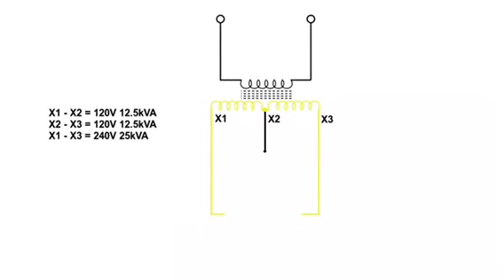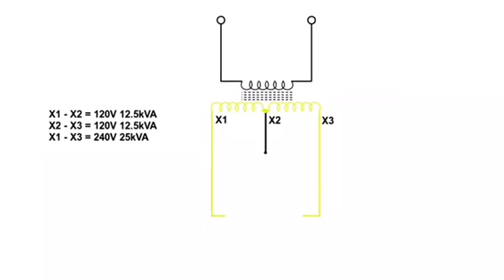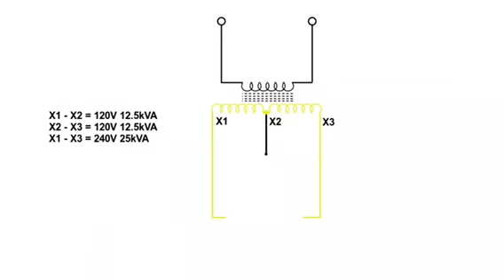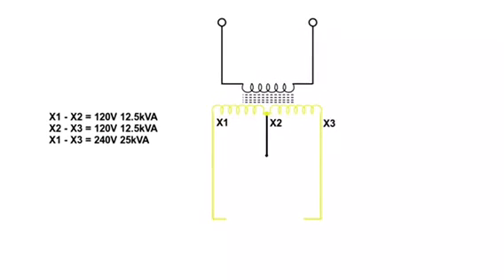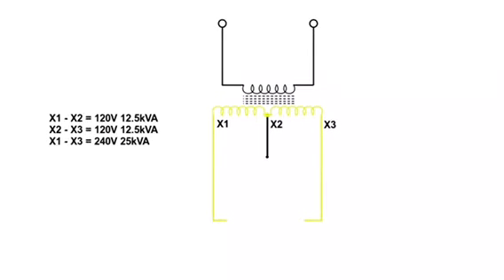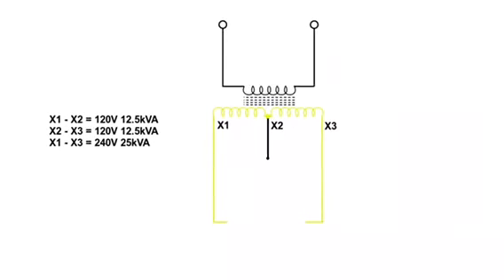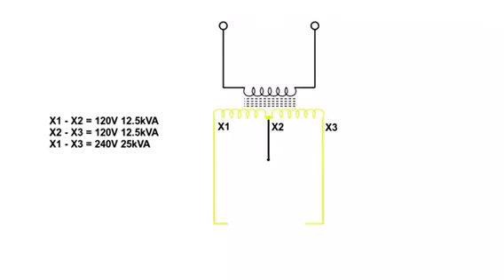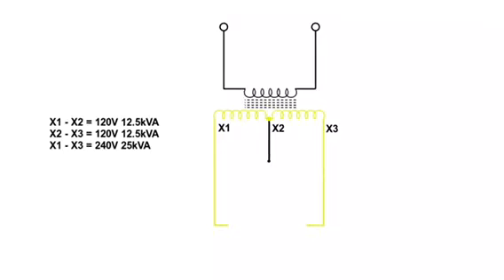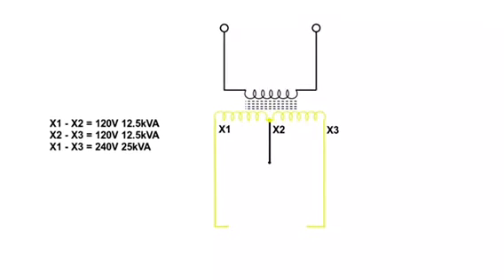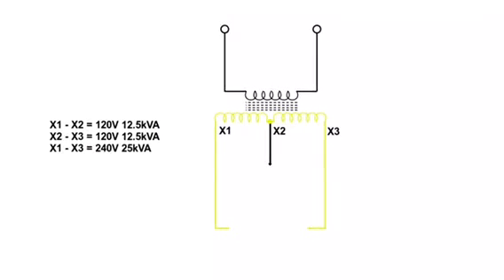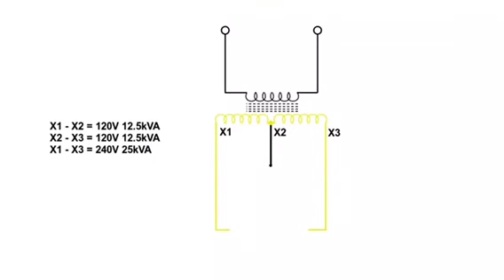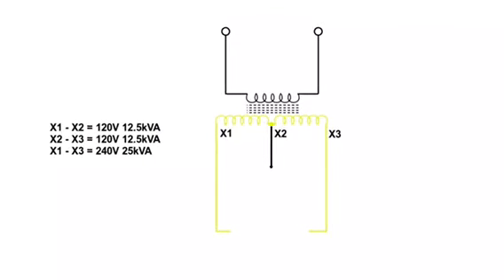Alright, so what you see here is a basic transformer. The upper part would be the high voltage. The lower part with X1, X2, X3 is going to be your low voltage and is depicting a center tap. This particular transformer we spec'd out at 25 kVA, so that's about 104 amps continuous across the X1 to X3 terminals.